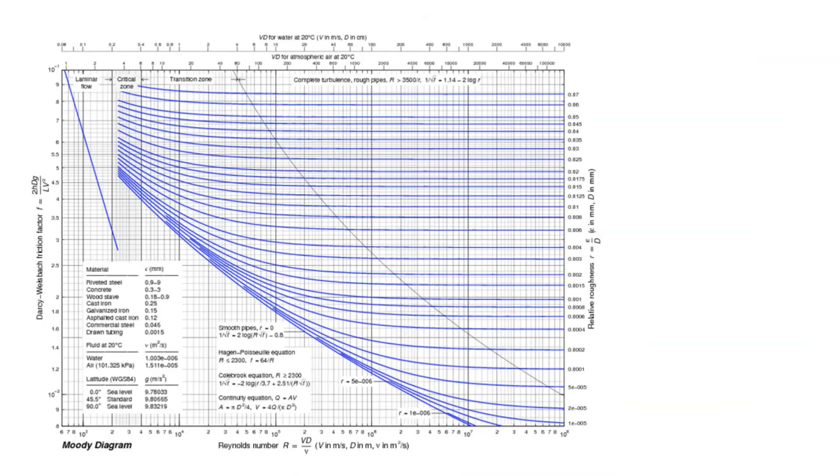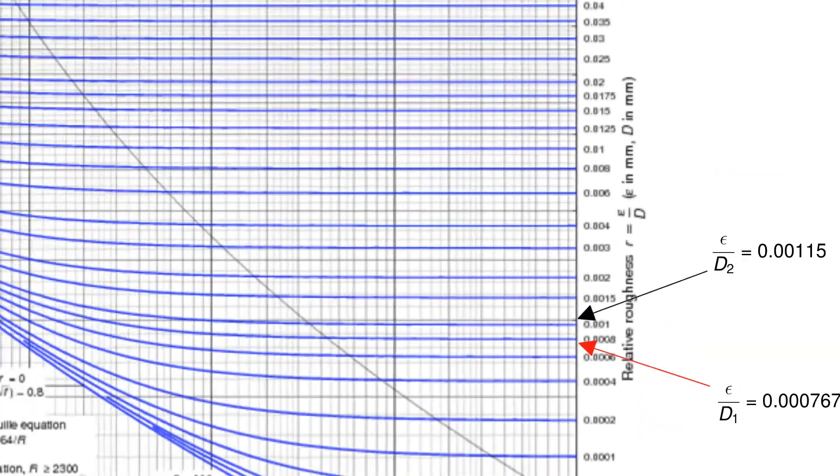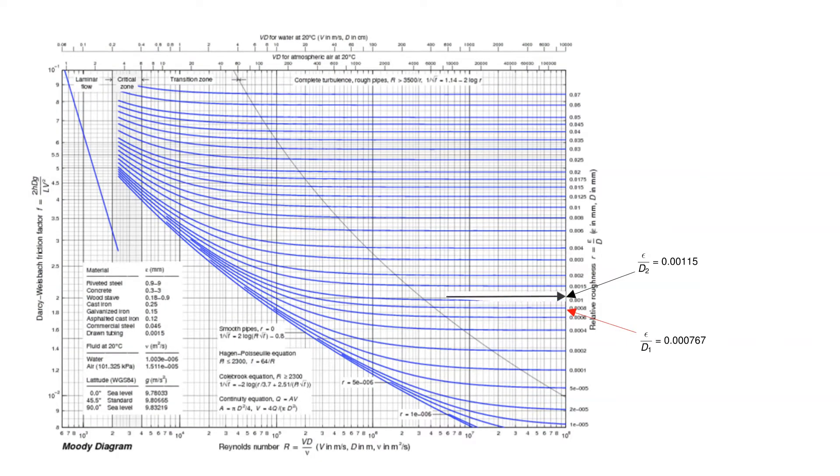The approximate relative roughness curves for both of the pipes are noted. Since we have to guess friction factors for each pipe, let's start with friction factors that are valid over a wide range of Reynolds numbers. We select a friction factor that is valid over the flat or horizontal portion of the relative roughness curves which occur at the higher Reynolds numbers.